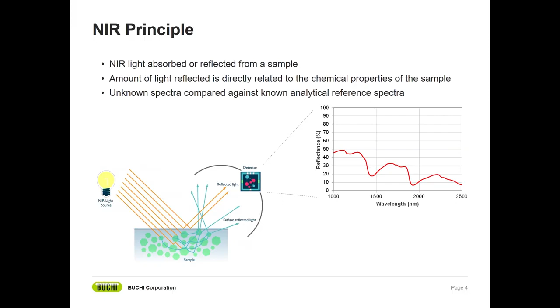If you visited the Büchi website, you've probably noticed a range of NIR instrumentation. Each one of these systems operates on the same principle, but has minor differences to allow users like yourself to choose the best instrument for the job at a price point that's most suitable for your budget. The Proximate on the far left is our newest to the portfolio, and we'll get into those details coming up. The NIR-Master and NIR-Flex operate using FT-NIR. The NIR-Master is the more rugged version with an IP65 rated outer shell to protect against dust and debris. The NIR-Flex has more accessories to allow you to modify how you present your sample to the instrument and is really tailored for clean R&D labs.